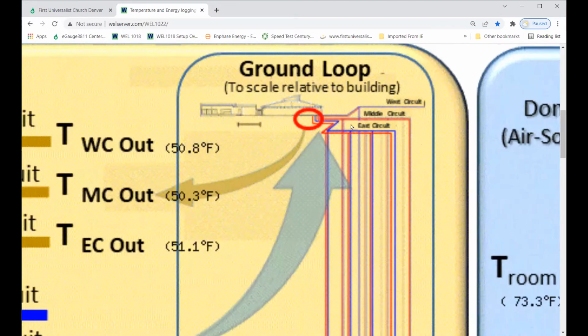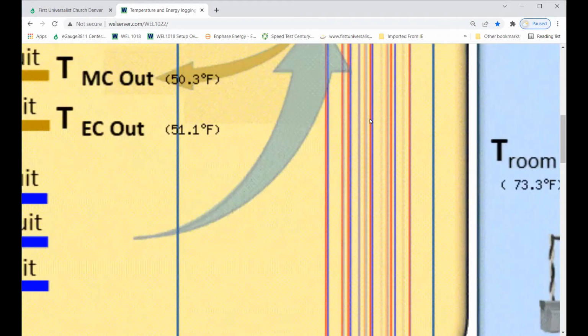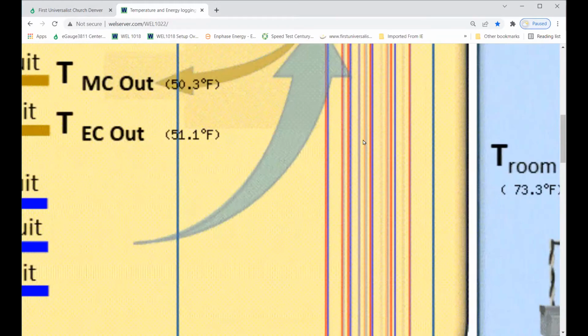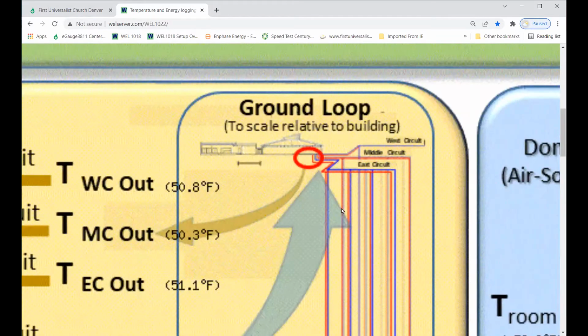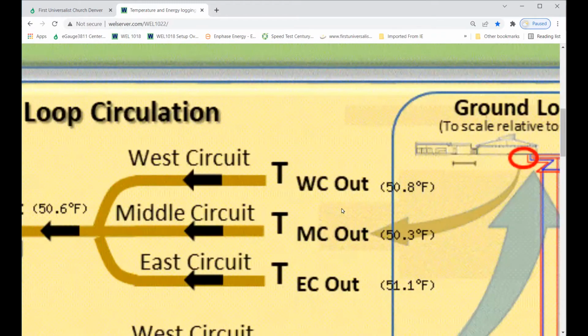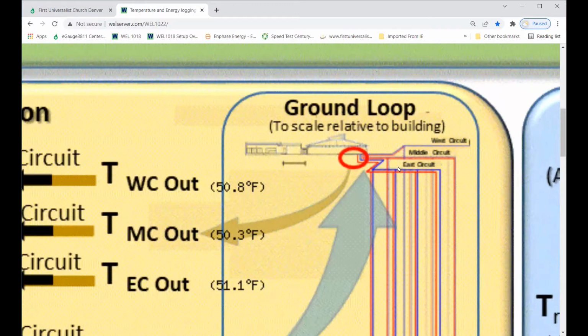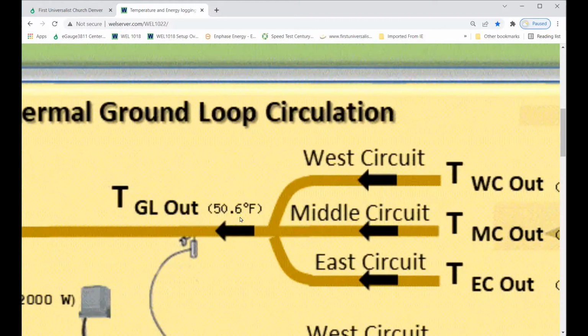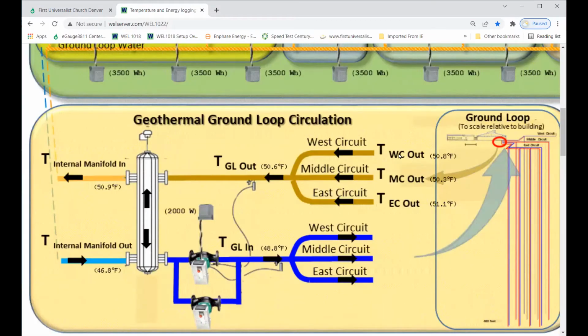And then out in the north parking lot, we have the ground loop with the boreholes that go down 400 feet and exchange energy with the earth, as I indicated. So those 12 boreholes are plumbed together into 3 different circuits. And what this depicts is that for each of the 3 circuits, the water comes in and we sample its temperature, which comes in around 50 degrees. It's mixed into a common pipe, about 4 or 5 inches, that goes throughout the building.